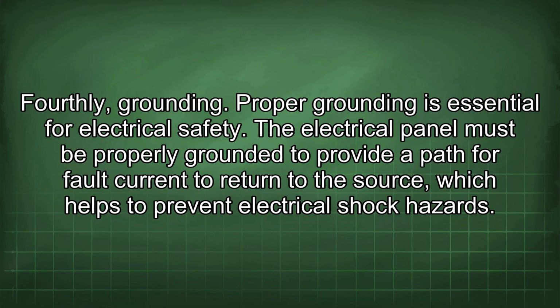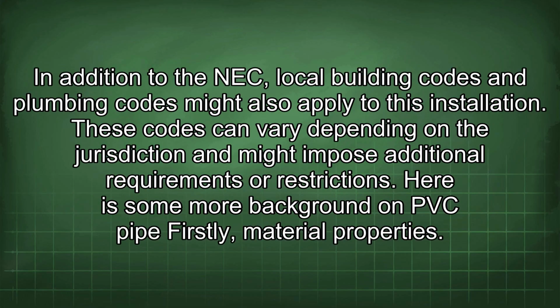Proper grounding is essential for electrical safety. The electrical panel must be properly grounded to provide a path for fault current to return to the source, which helps to prevent electrical shock hazards. In addition to the NEC, local building codes and plumbing codes might also apply to this installation. These codes can vary depending on the jurisdiction and might impose additional requirements or restrictions. Here is some more background on PVC pipe.